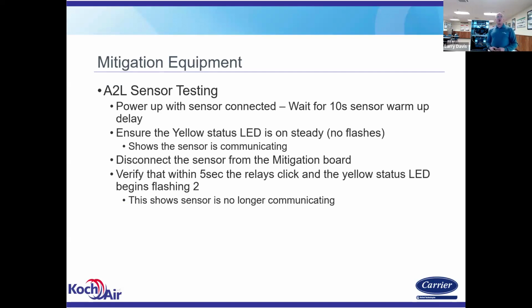We walked through the process of testing the sensor and getting those 5-volt DC measurements. Again, there are four wires running to the sensor. The outer two are the 5-volt DC power supply to the sensor. The middle two are communicating. If you unplug the sensor from the board, you should lose communication to the sensor and throw a fault. If you walk up and it's plugged in and it's showing that fault, that's when you're going to unplug and check those voltages.